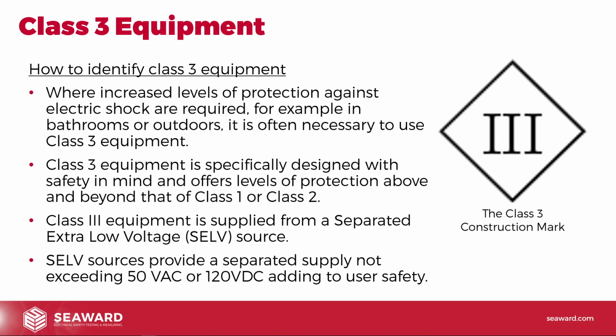So by the time you add all that up, that's why SELV systems or Class 3 systems are used in things like bathrooms, used outside in gardens, maybe the Christmas lights, things like that you might come across are Class 3. Quite often people get confused with things like phone chargers and say, oh yeah, phone charger, that's Class 3. No, it isn't. There's several reasons for that. The main reason being it's connected to the mains. So because it's connected to the mains, the highest voltage present inside there is 230 volts, in which case it's not SELV, so it can't be Class 3 anyway. But generally most of those things like phone chargers are going to be Class 2.